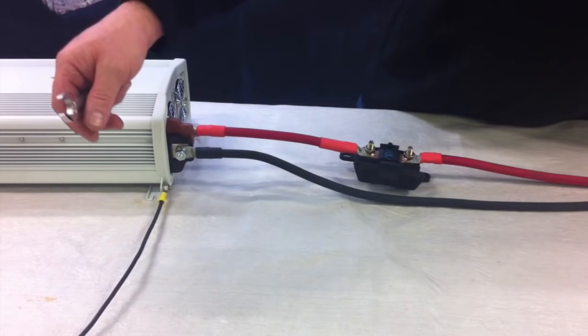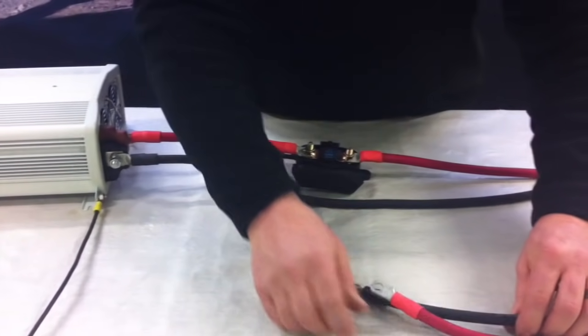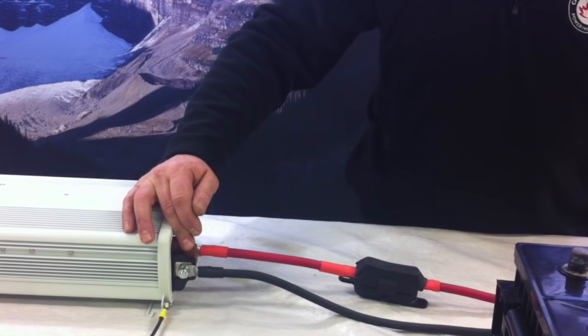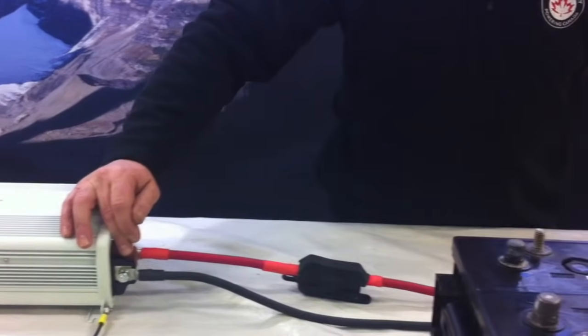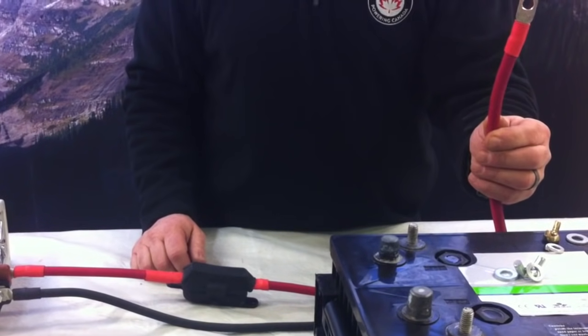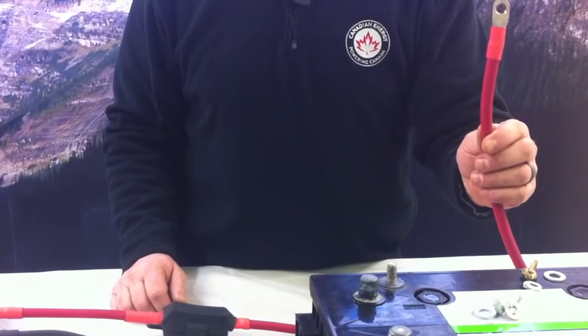Next we're going to go ahead and we're going to bring on our 12 volt battery source. Now that we've got our inverter connections made we're going to go and hook up the 12 volt battery. So what we want to do first is make sure we hook up our positive cable first. And I'll get to the reason why in just a minute.